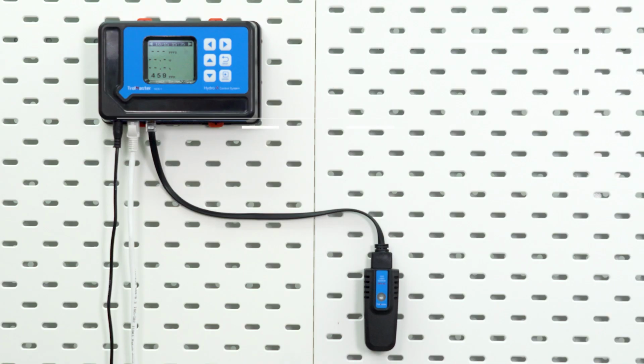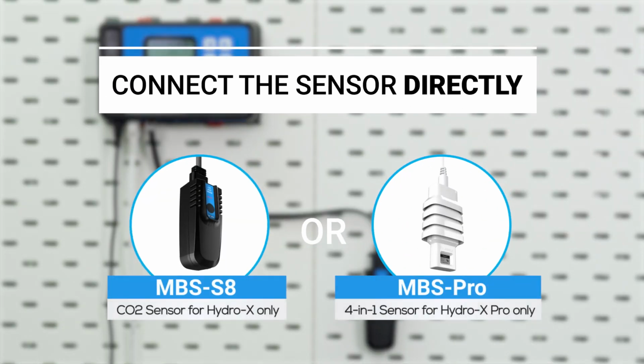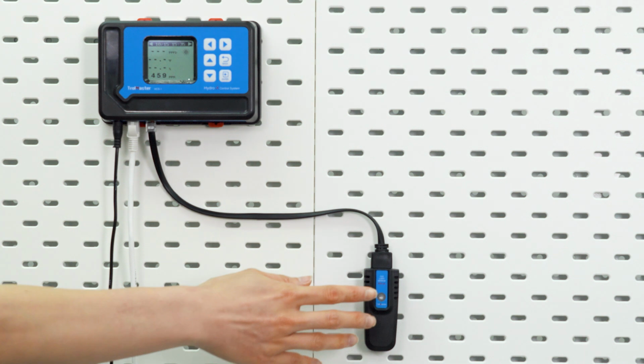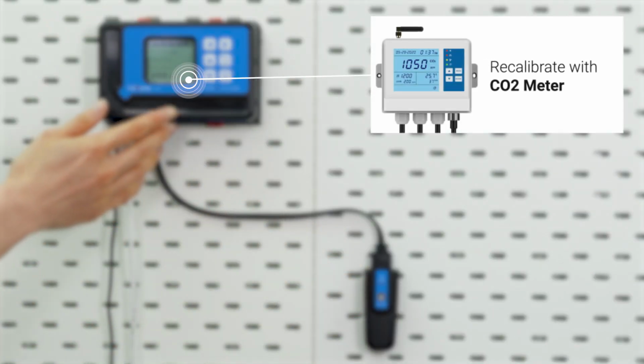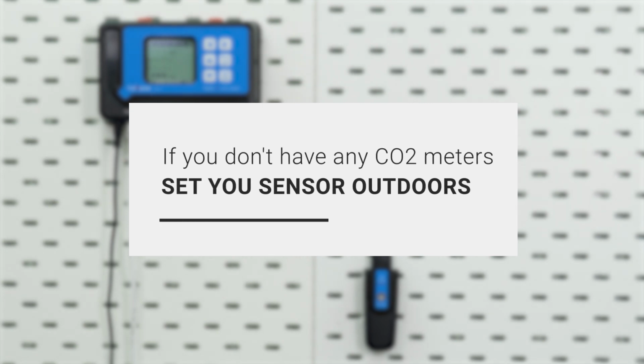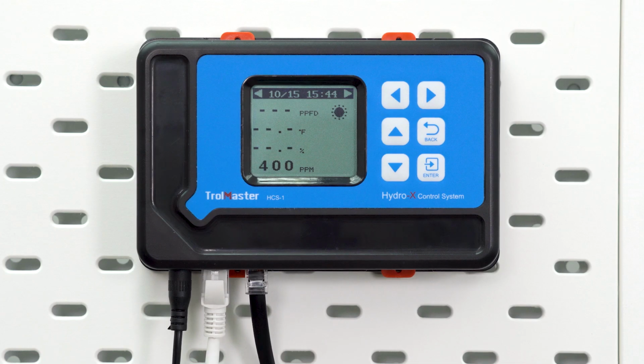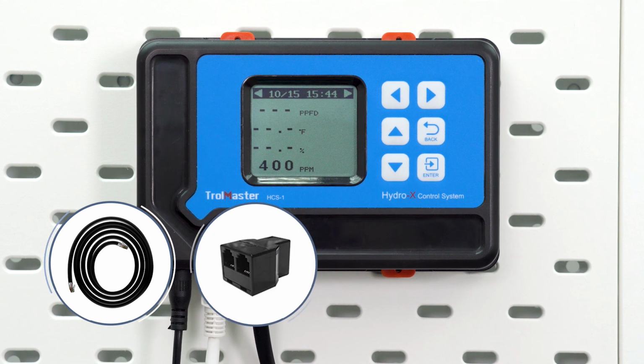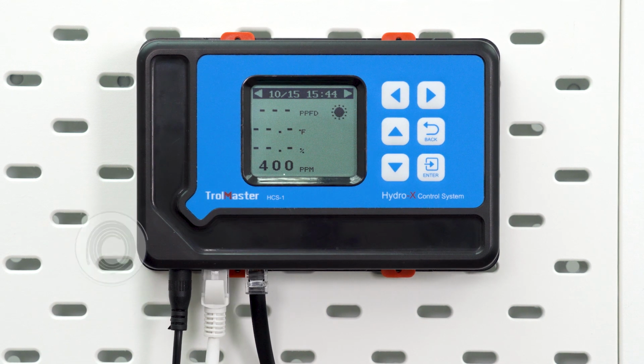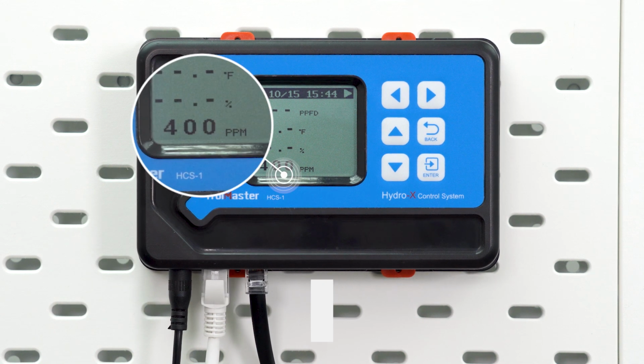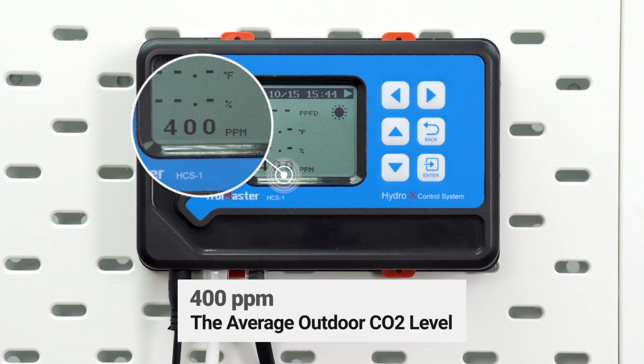To calibrate your CO2 sensor, connect it directly to the controller sensor port. If you have a third-party CO2 meter, recalibrate with it. If you don't have any CO2 meters, set your sensor outdoors. Extend it with cables and Y splitter if you have to. Recalibrate it to 400 ppm, which is the average outdoor CO2 level.